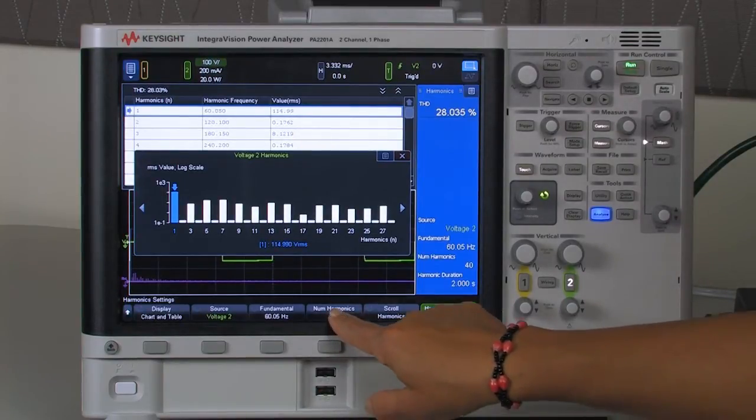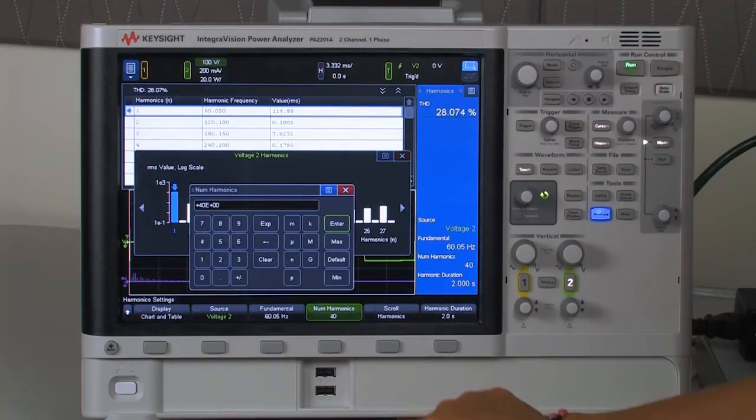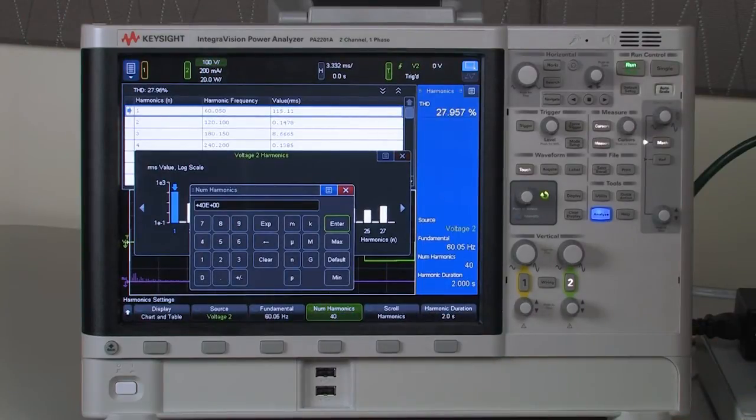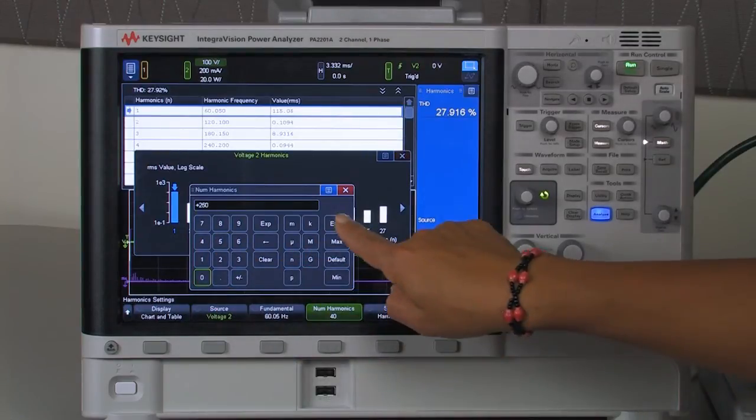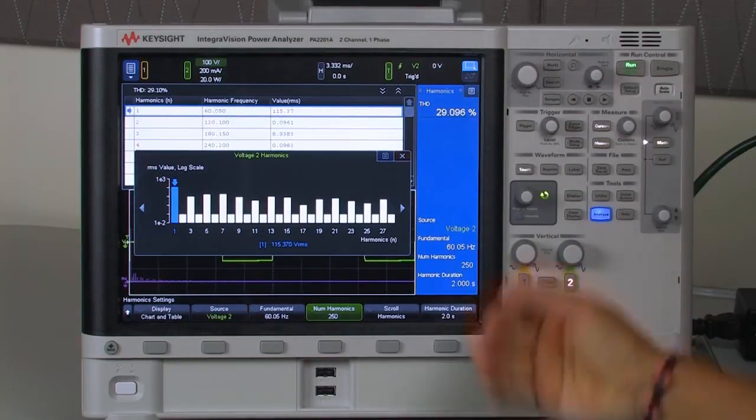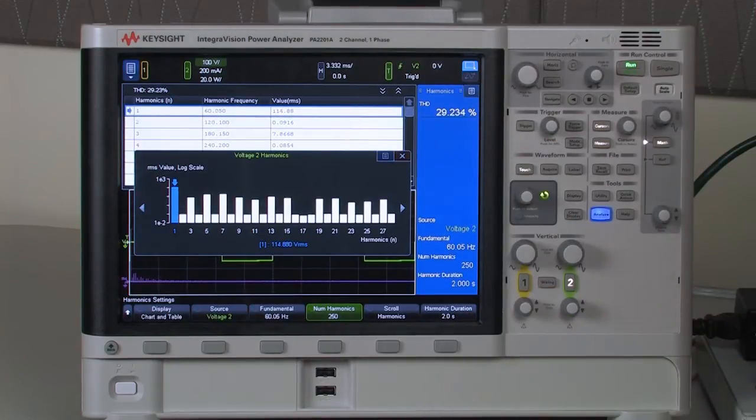Now as default it's set to 40 harmonics but I can go for line frequency as high as 250 which obviously will give me a more precise reading. Now it seems like I have about 29 percent of distortion.